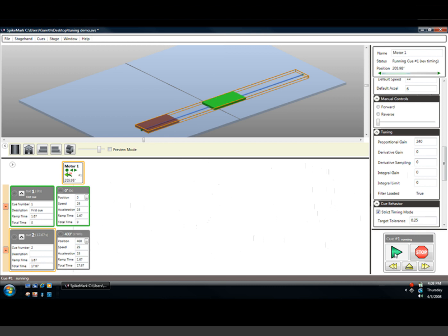I had a little funny hiccup at the beginning. Yeah, it's starting to become unstable at the end of travel. Let's double that again and see what happens. And now it is really having trouble at the beginning of the move. It was shaking back and forth as we started the move. And it'll probably shake back and forth here during the deceleration as well. Yes, indeed. And we lost our accuracy because of that shaking.